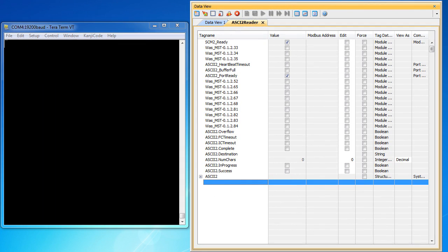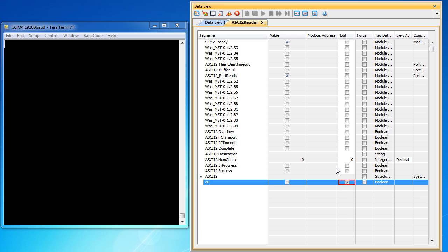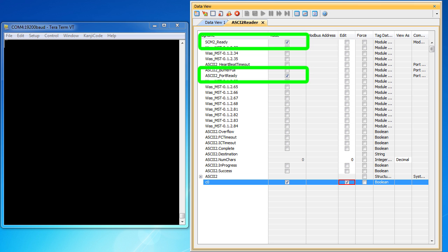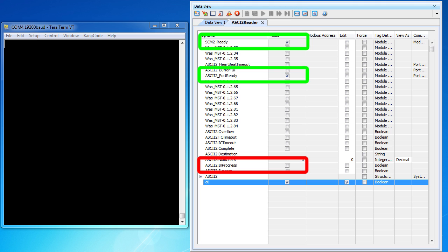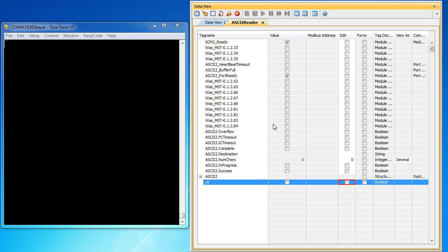Here's our data view and terminal side by side. Let's add the control bit and use it to enable the ASCII IN instruction. Hmm, we see the module is ready, the port is ready, but the ASCII IN instruction is not active. Why not? Well, we took the controller out of run mode back when we auto detected the hardware, right? Flip that switch back to run and sure enough, now the ASCII IN instruction is telling us it's running.